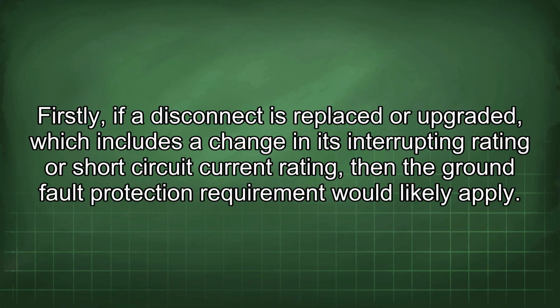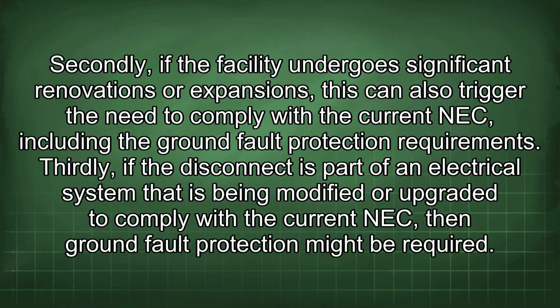Firstly, if a disconnect is replaced or upgraded, which includes a change in its interrupting rating or short circuit current rating, then the ground fault protection requirement would likely apply. Secondly, if the facility undergoes significant renovations or expansions, this can also trigger the need to comply with the current NEC, including the ground fault protection requirements. Thirdly, if the disconnect is part of an electrical system that is being modified or upgraded to comply with the current NEC, then ground fault protection might be required.